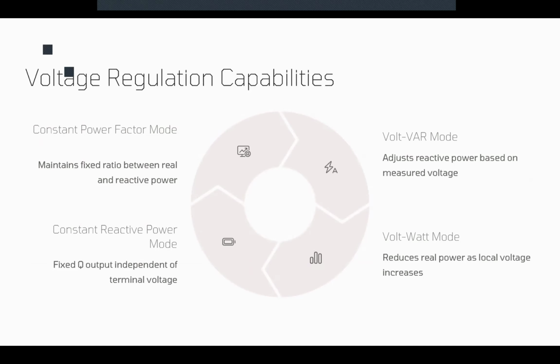Now, another aspect that we mentioned is the voltage regulation capability. Okay, we talked about that. We could have several protocols to help the voltage stability and regulation of the local voltage at the PCC. One would be the constant power factor mode, which basically maintains the ratio between the real and reactive power. IEEE specifies that DER should be capable of operating continuously within that range of a power factor that we define, which is primarily used when the utility wants a static voltage support and minimal real-time variability.